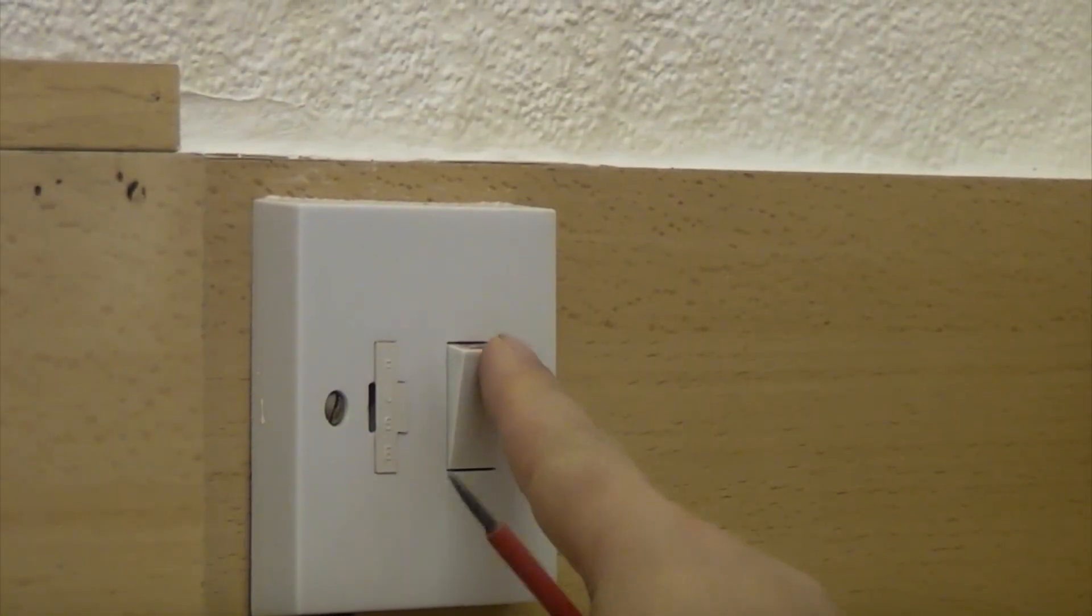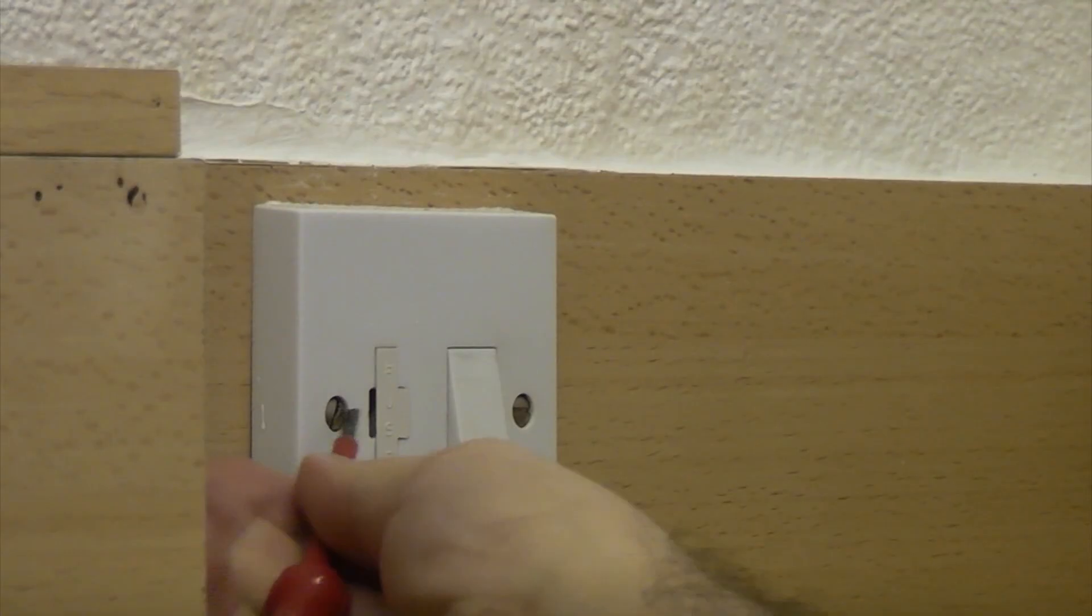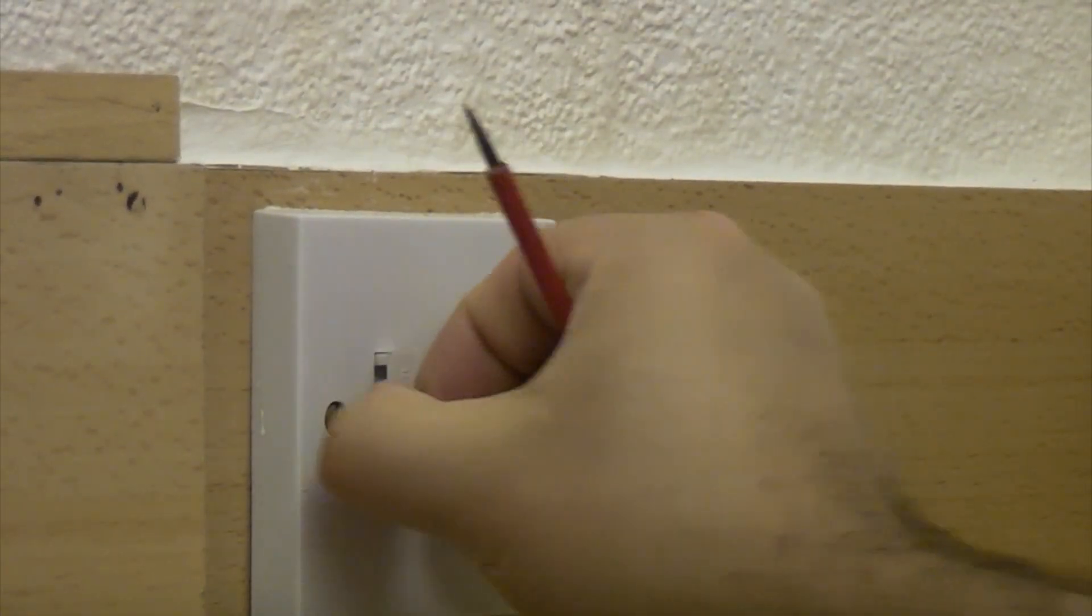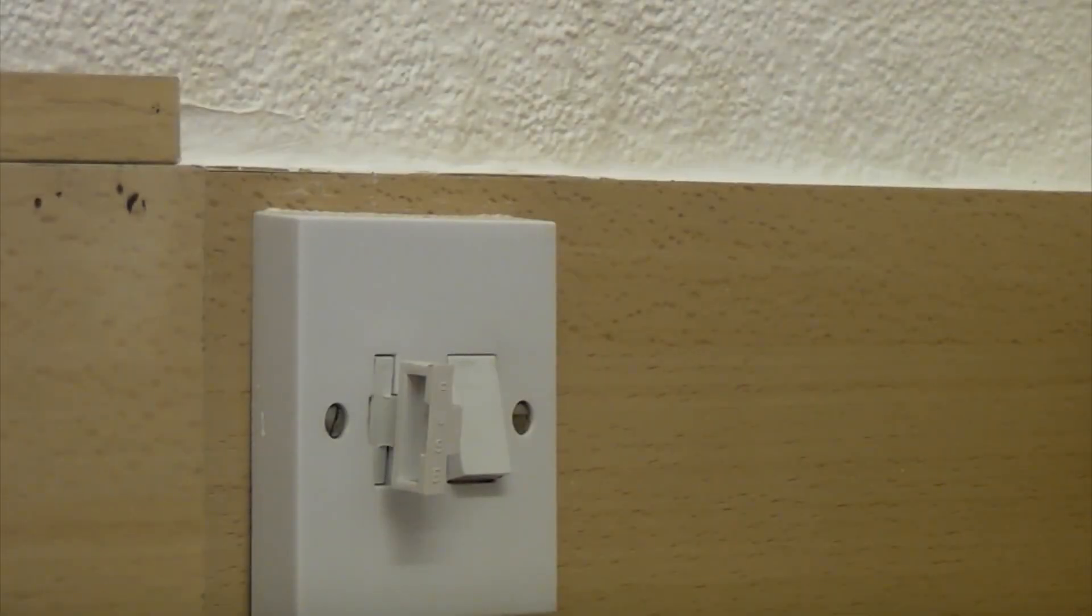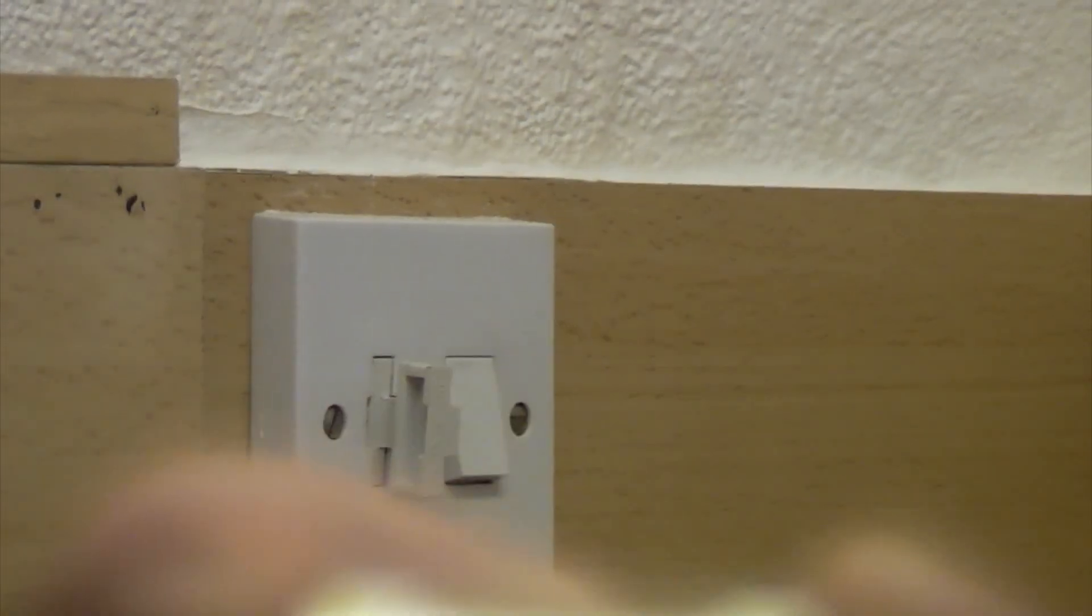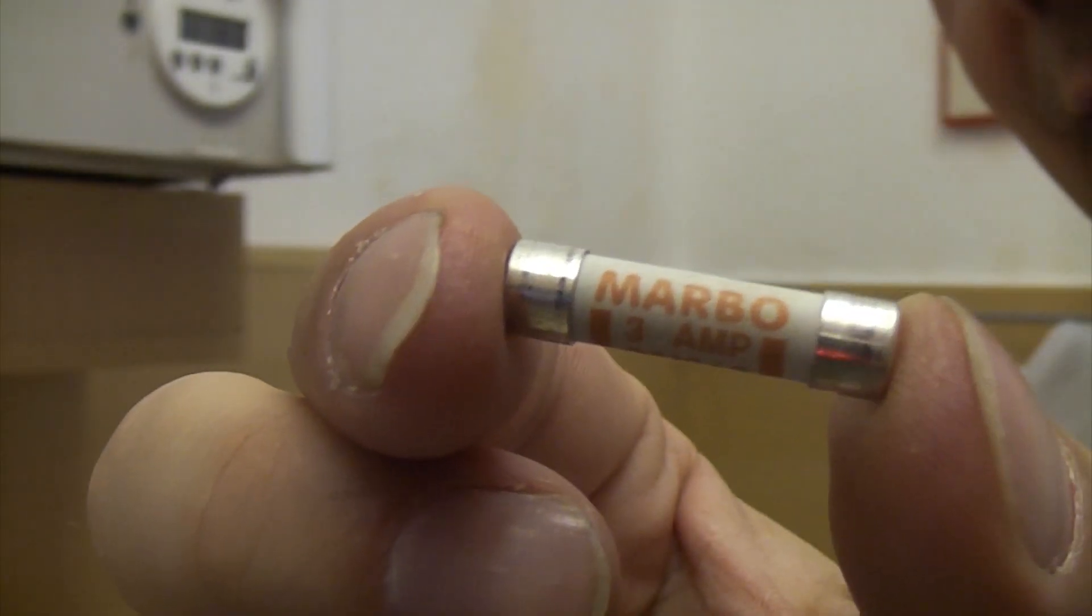So before we start, we are going to switch the boiler off, and we are just going to pop the fuse out of there just to be on the safe side. So we will take the fuse out, and also it is actually a 3 amp fuse, which is perfect because it should be less than 5 amps.